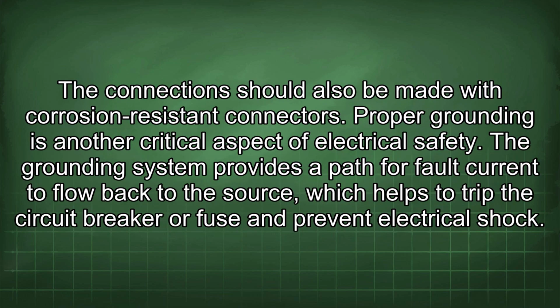The connection should also be made with corrosion-resistant connectors. Proper grounding is another critical aspect of electrical safety. The grounding system provides a path for fault current to flow back to the source, which helps to trip the circuit breaker or fuse and prevent electrical shock.